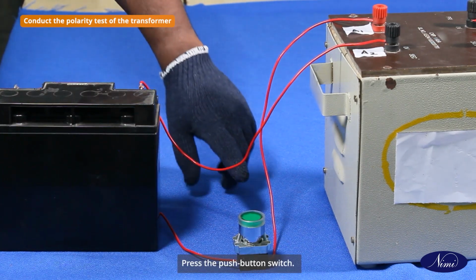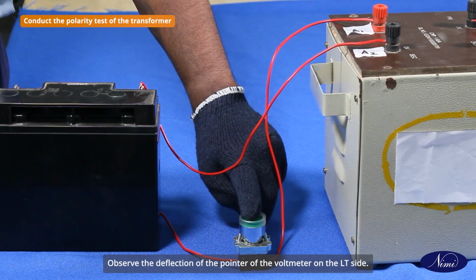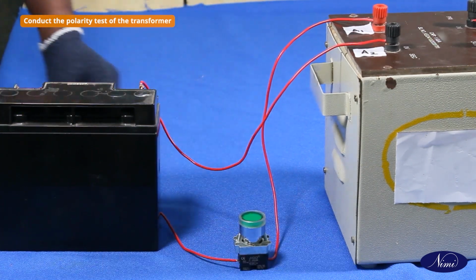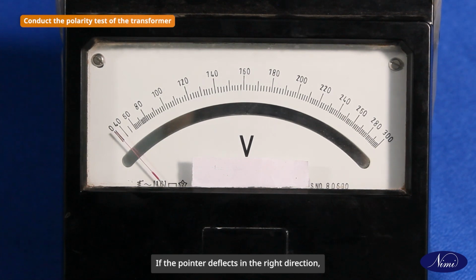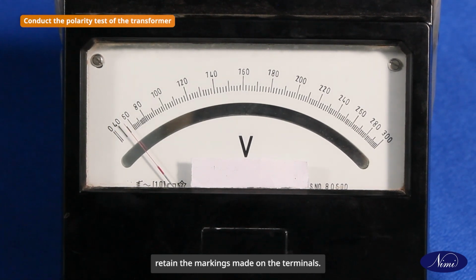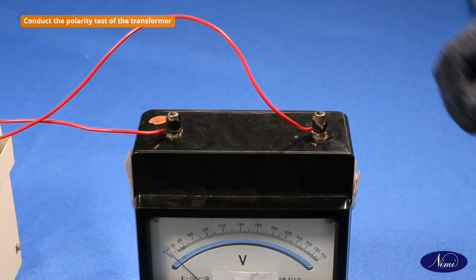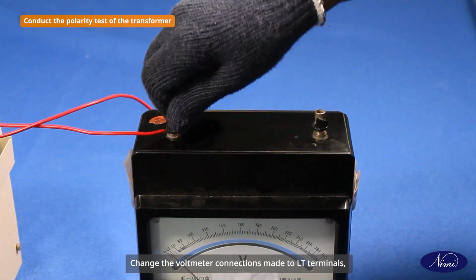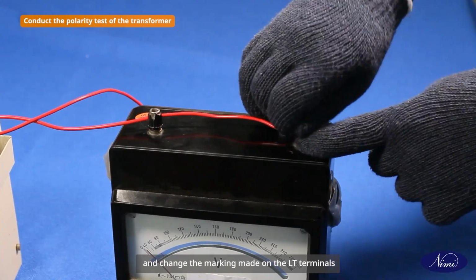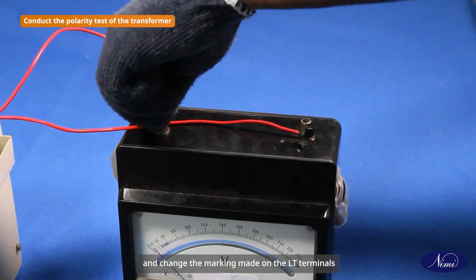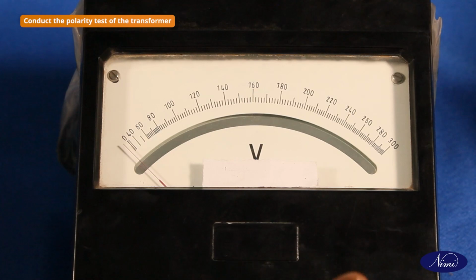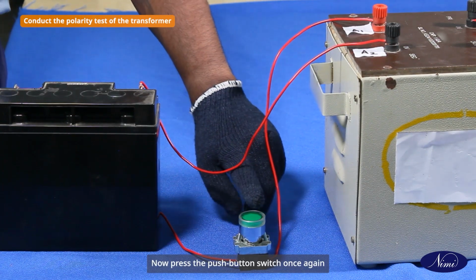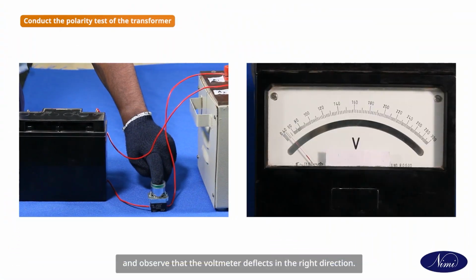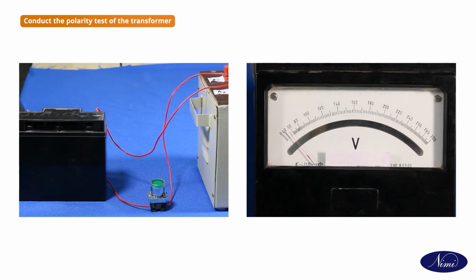Press the push button switch. Observe the deflection of the pointer of the voltmeter on the LT side. If the pointer deflects in the right direction, retain the markings made on the terminals. Change the voltmeter connections made to the LT terminals and change the markings made on the LT terminals if the deflection is in the reverse direction. Now press the push button switch once again and observe that the voltmeter deflects in the right direction.